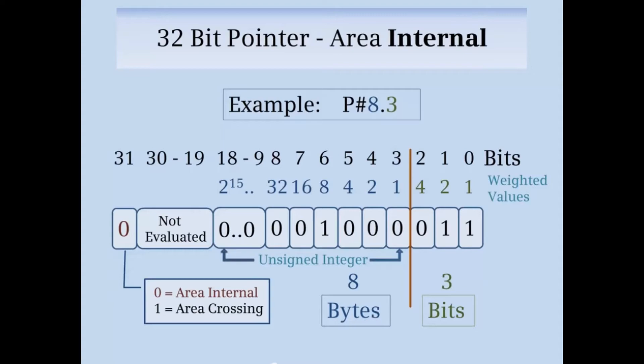For example, consider the area internal address P#8.3. The bits would be stored in the fashion shown. Bits 0 to 2 would contain 1, 1, 0 making up the decimal value 3. There would be a 1 in bit 6 with weighted value 8 making up the byte part of the address. This bit pattern would be the area internal address P#8.3.